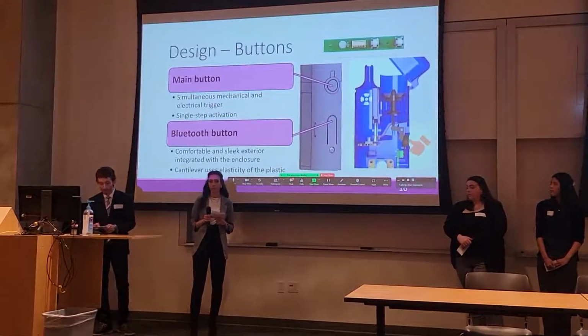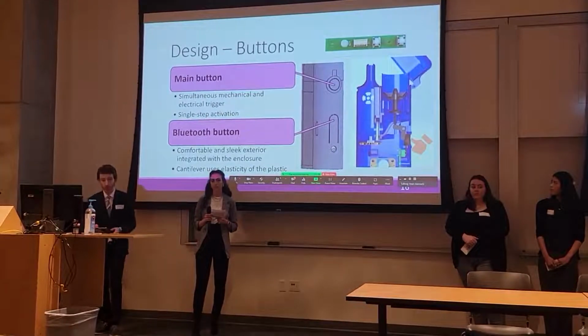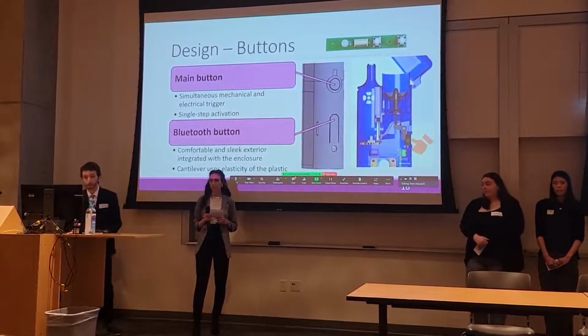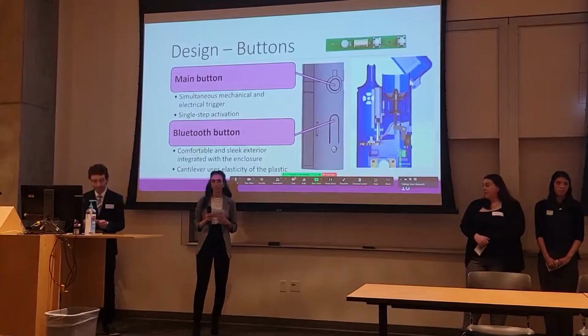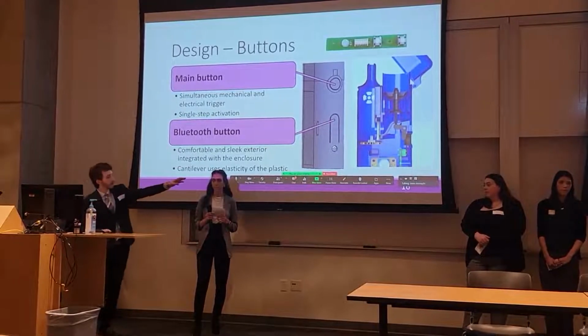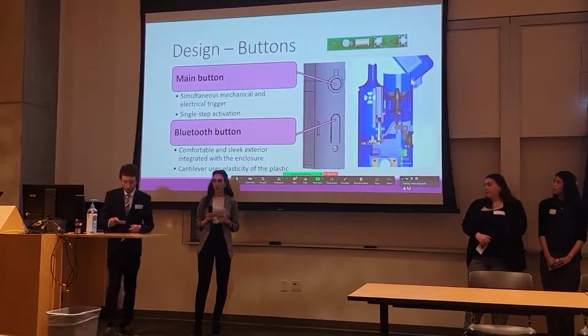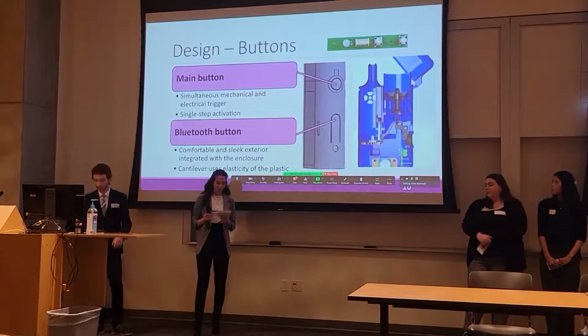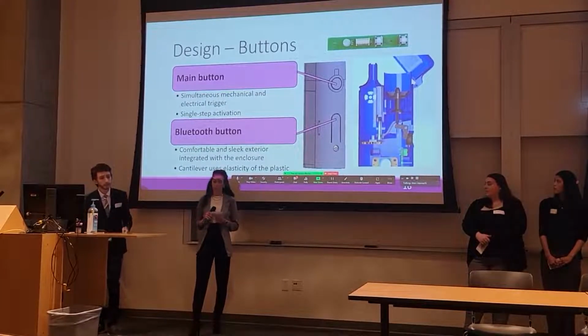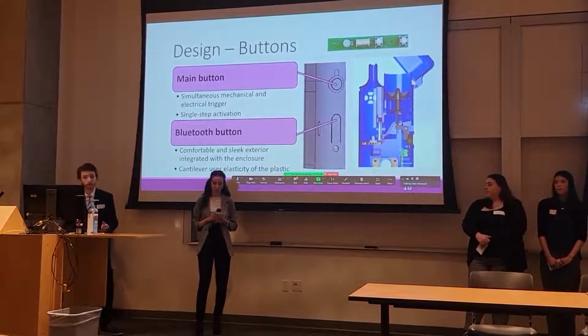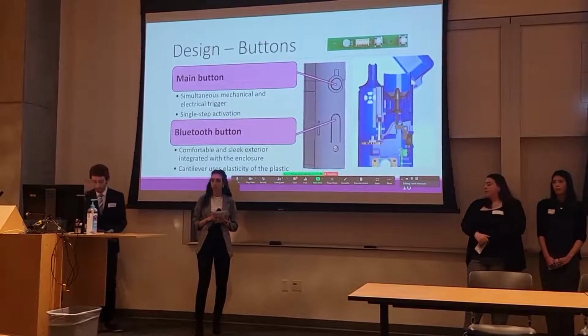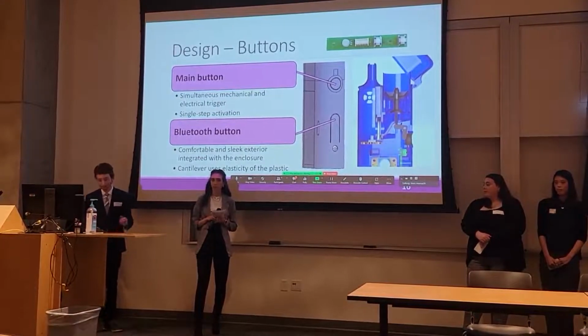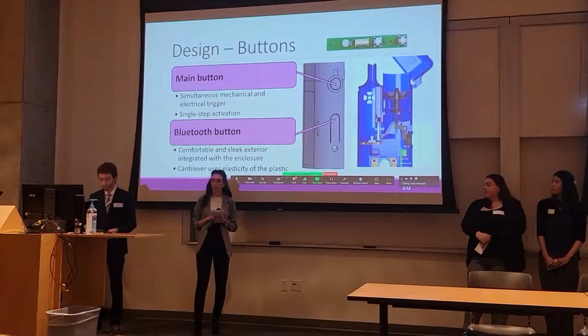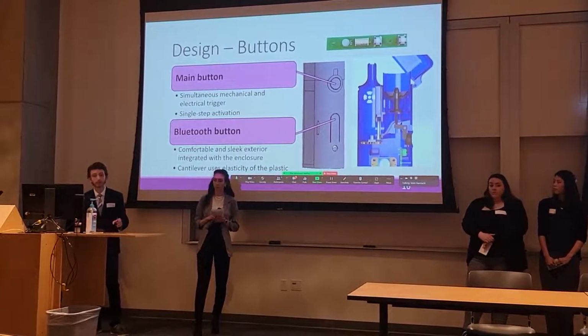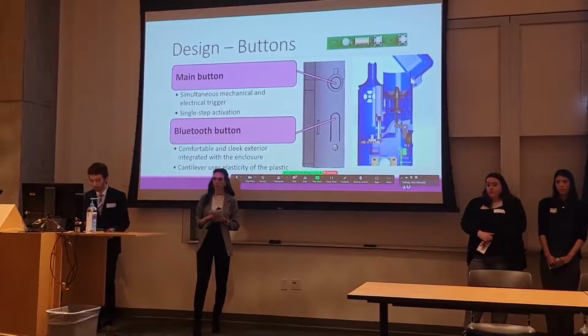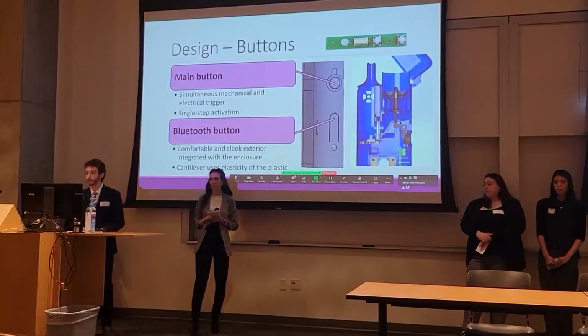The nebulizer's main button uses a mechanical lever to release medication from the capsule valve and simultaneously triggers the electrical button in green to turn on the device, for simple, single-step activation during the stress of an asthma attack. To reduce the number of parts compared to that main button, the Bluetooth connectivity button is built into the housing and uses the elasticity of the plastic to reliably spring the lever back into place.